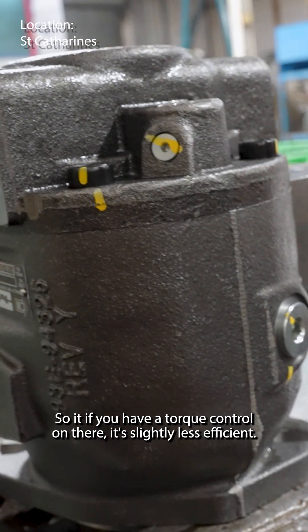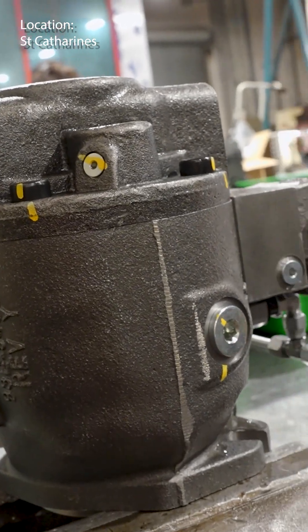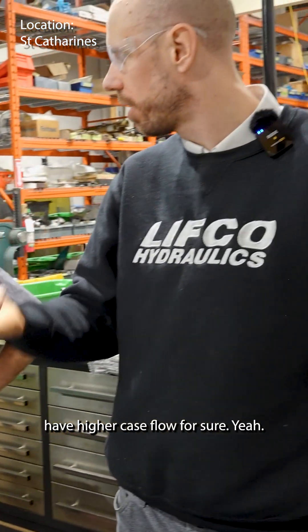The 140s, the big guys — they all did those first, and then the 45s are the smallest. So the torque limiter is only available from the 45 to the 100. The torque control uses up some of the oil; if you have a torque control on there, it's slightly less efficient. Once you get into the very smaller sizes, that efficiency becomes more of an issue.